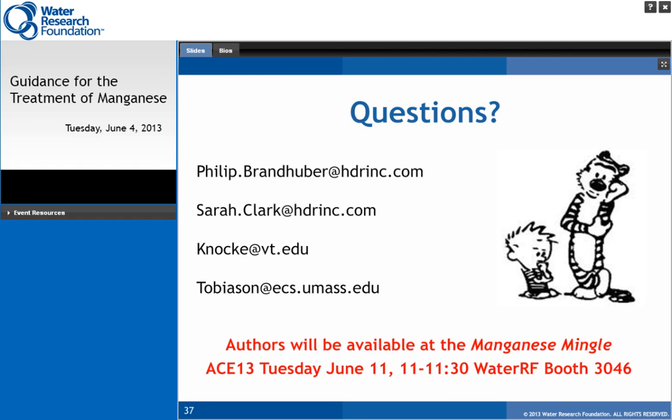A question regarding toxicity: is there a certain level at which manganese is toxic to bacteria? From a practical standpoint, the levels of manganese typically seen in drinking water situations are well below any levels of toxicity. Biologically-based systems have been operating at perhaps up to a milligram per liter of soluble manganese without toxic effects on the bacteria. Most groundwater applications I've seen are at a half milligram per liter or less, with no indications of a toxic response.